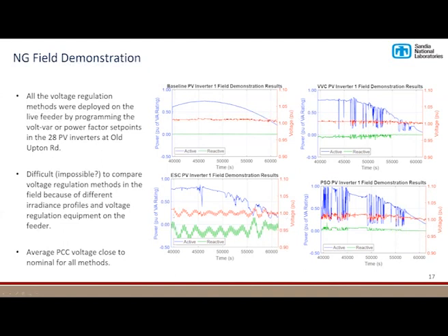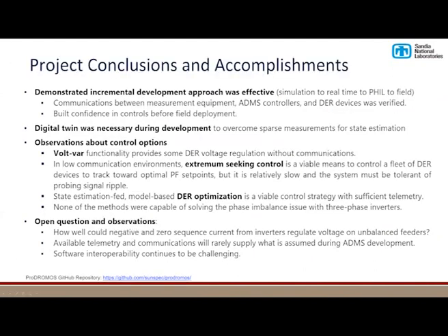One per unit. And you can see, in the extremum seeking control case, the reactive power ripple and its influence at the point of common coupling. If the system is sensitive to that, that's not too good. But in the case of the particle swarm optimization, again, it's operating relatively close to nominal and just sitting there pretty much for the whole run. So, in conclusion, we demonstrated that this incremental approach, moving from pure simulation to real-time simulation to the hardware-in-the-loop environment and then a field demonstration, was a good approach.